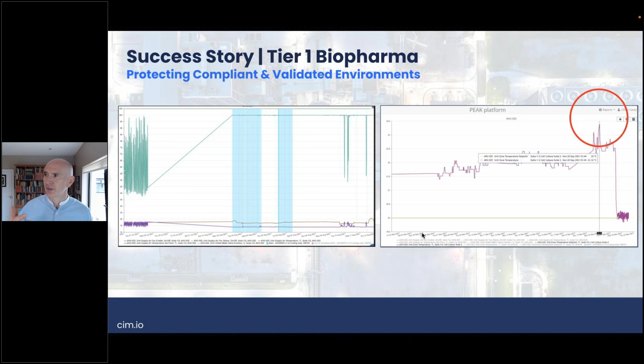And ultimately, the cause here was a strainer that was right before the coil, and even though the valve was open 100%, the strainer was blocked, and the chill water couldn't make its way into the coil, so it couldn't achieve cooling, and the temperature was increasing incrementally. So what the analytics did in this instance was it detected that in a really short period of time. It assigned the action to the maintenance team and told them exactly what they needed to do to address this issue. And those guys went up and addressed it. And again, the issue was resolved without any compliance or any kind of impact to quality. So this was an immensely beneficial way of proving the value of data analytics over and above what BMS alarms do.